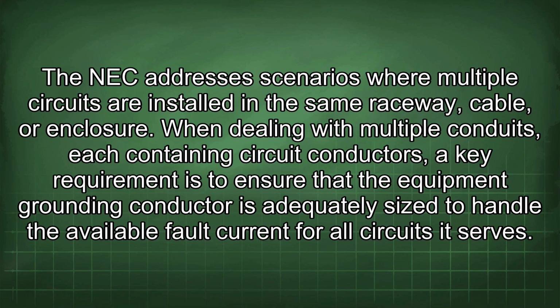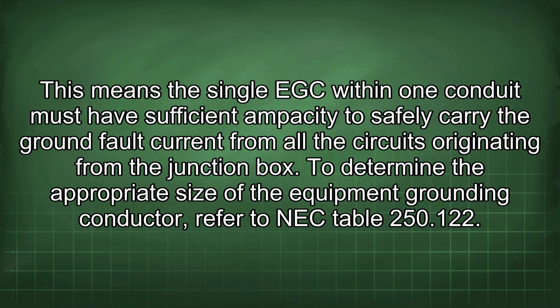When dealing with multiple conduits, each containing circuit conductors, a key requirement is to ensure that the equipment grounding conductor is adequately sized to handle the available fault current for all circuits it serves. This means the single EGC within one conduit must have sufficient ampacity to safely carry the ground fault current from all the circuits originating from the junction box.